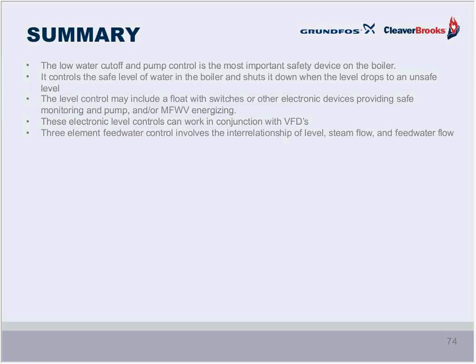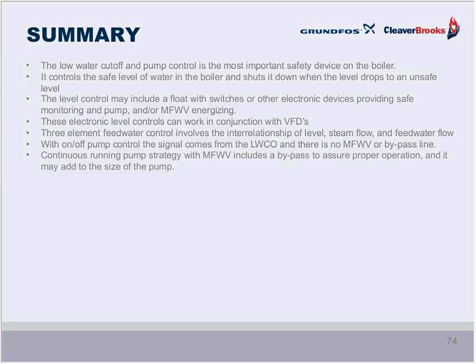Three-element feedwater control involves the interrelationship of level, steam flow, and feedwater flow. With on-off pump control, the signal comes from the low-water cutoff, and there is no modulating feedwater valve or bypass line. Continuous running pump strategy with the modulating feedwater valve includes a bypass to ensure proper operation, and it may add to the size of the pump, as Jim explained. A continuous running pump with variable frequency drive and modulating feedwater valve also requires a bypass line to compensate for no or low flow conditions.